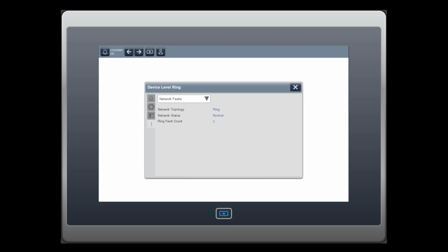Common fault: the ring fault usually occurs when one or more links is broken, or a node is taken off the network. An unexpected loop detected fault occurs when the network ring was closed without defining at least one node as a supervisor in linear topology. A partial network fault occurs when the active ring supervisor detects a network fault in one direction only.